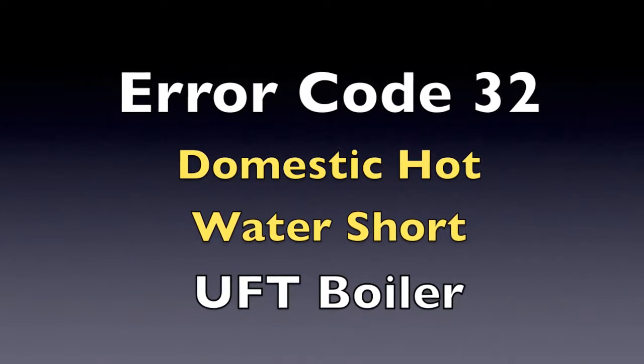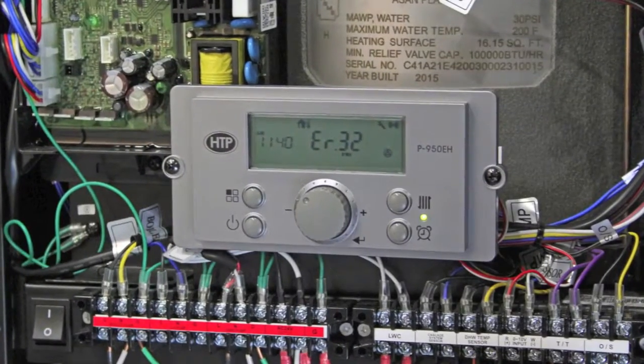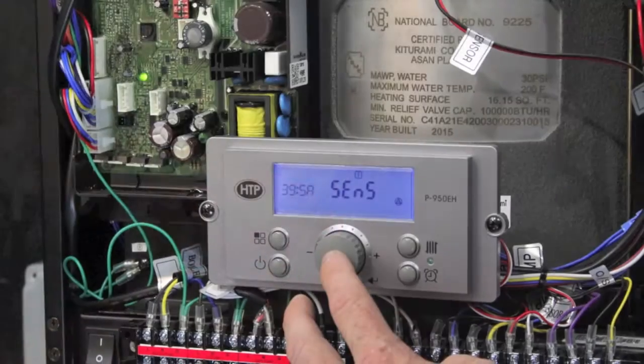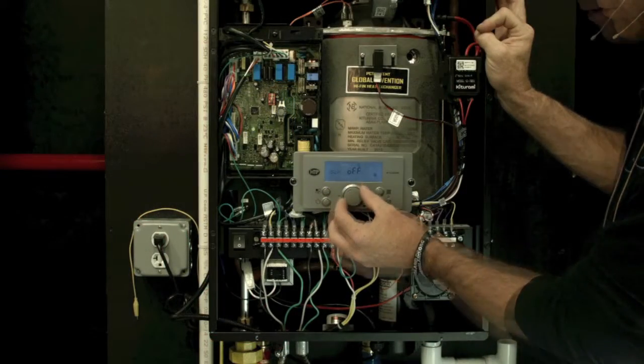Error 32 domestic hot water short, UFT models only. This error can appear if an Aquastat is installed and function 39 in the installer menu is set to sensor, or the sensor has become shorted.